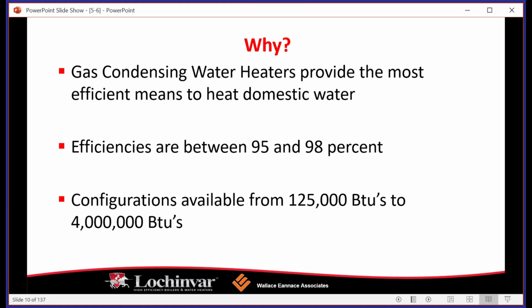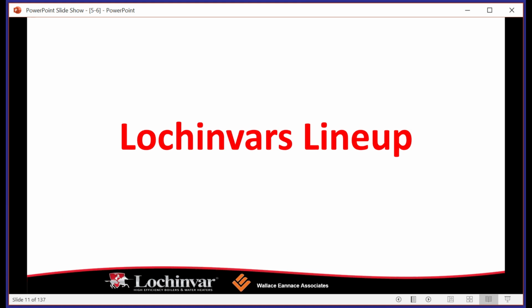So we discussed this a little bit. For water heating on the other side, 95 to 98% efficiency. Gas condensing water heaters are the most efficient ways to heat domestic water. So the technology that you see for a gas condensing modulating boiler is going to be the same for a water heater. The big differences between them are, of course, materials, because you're dealing with potable water that's going to be going out through faucets and fixtures. People are going to bathe in it, they're going to cook, they're going to drink it. So where you would see a boiler, you may have some cast iron or something like that. You're going to have all stainless and bronze and brass throughout a water heating piece of equipment.